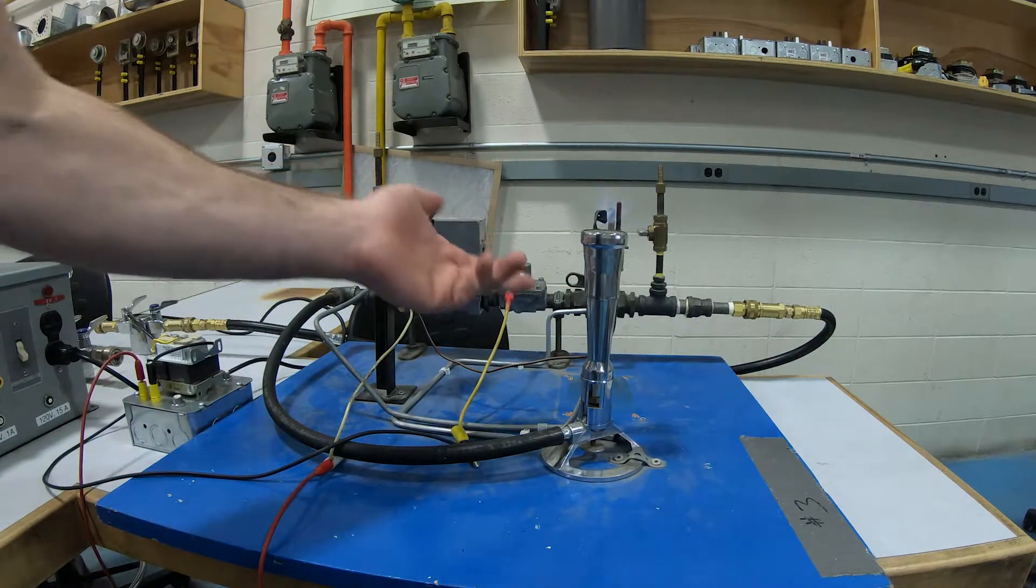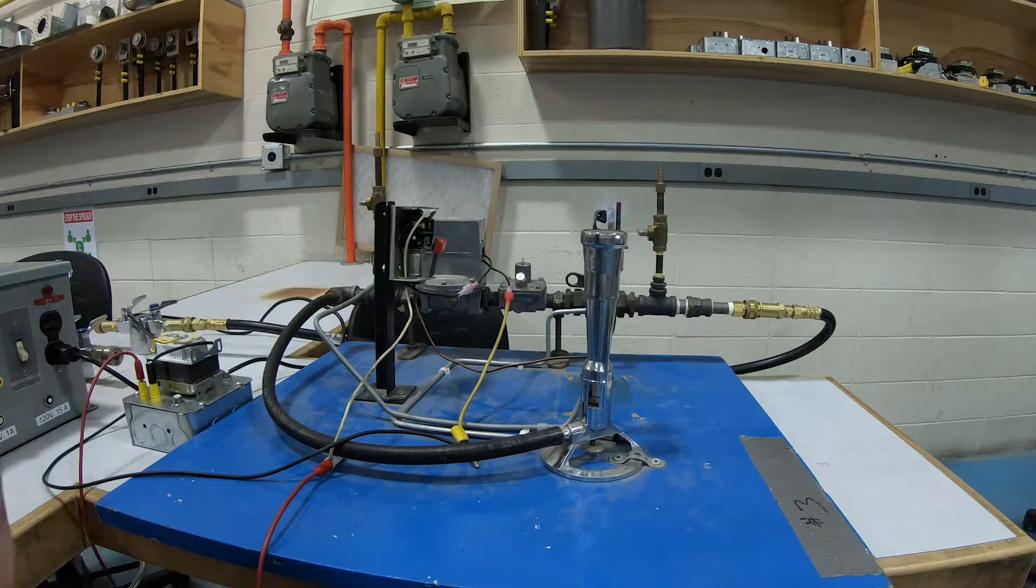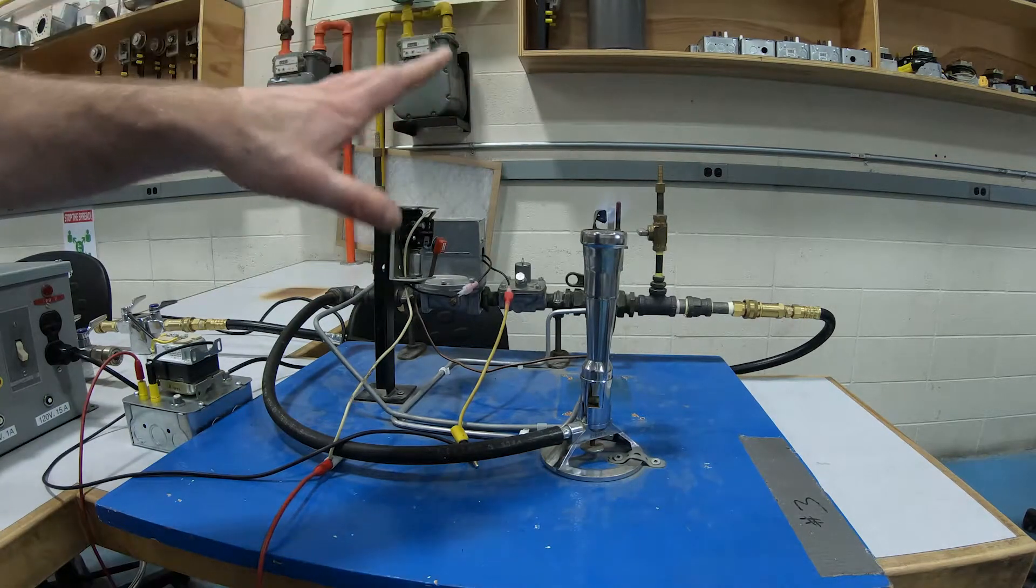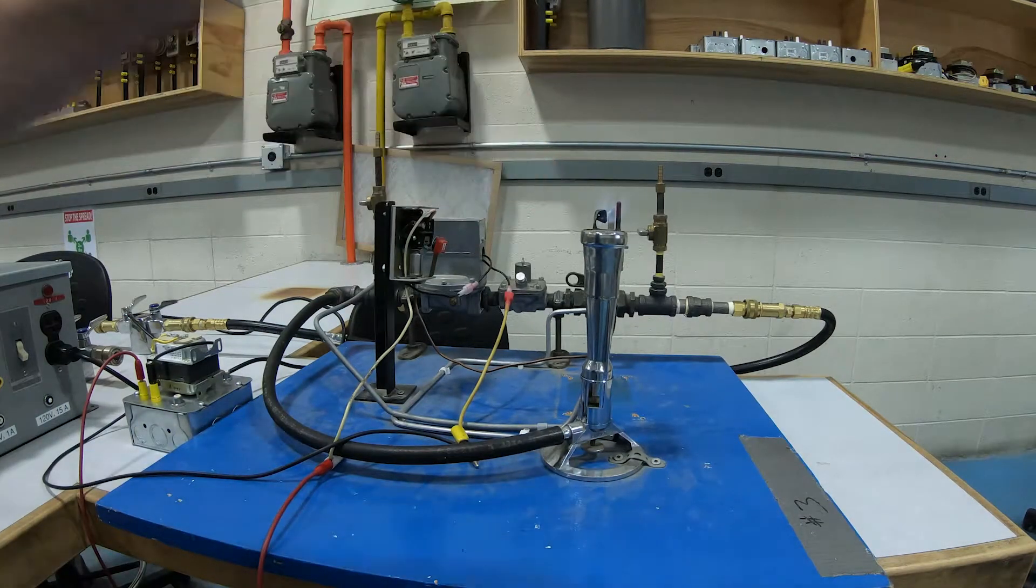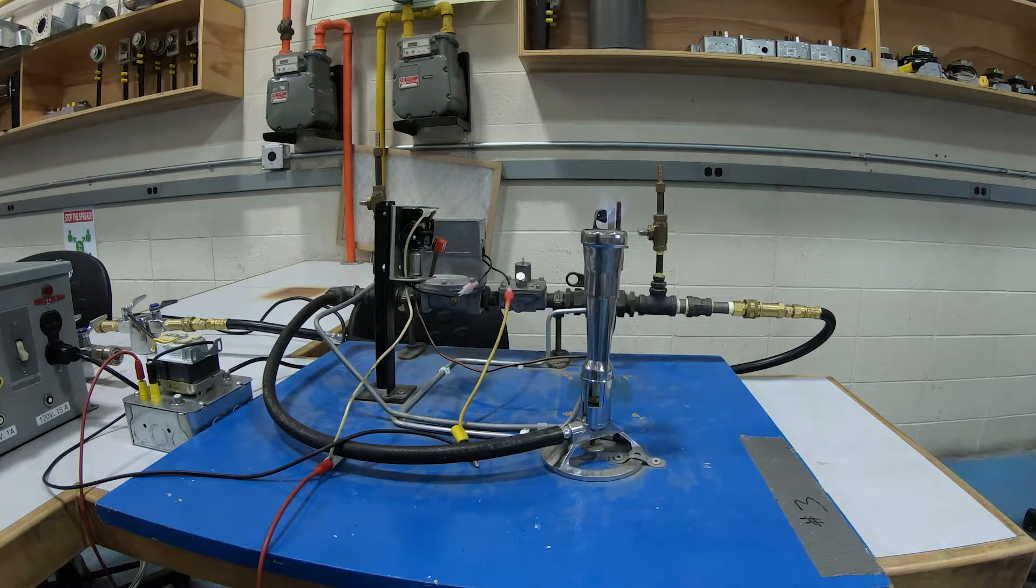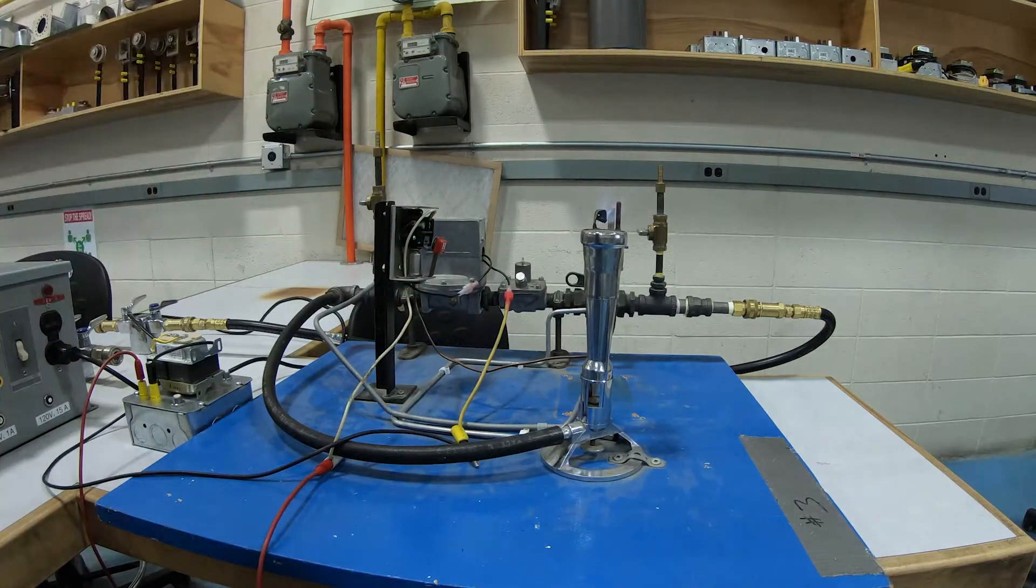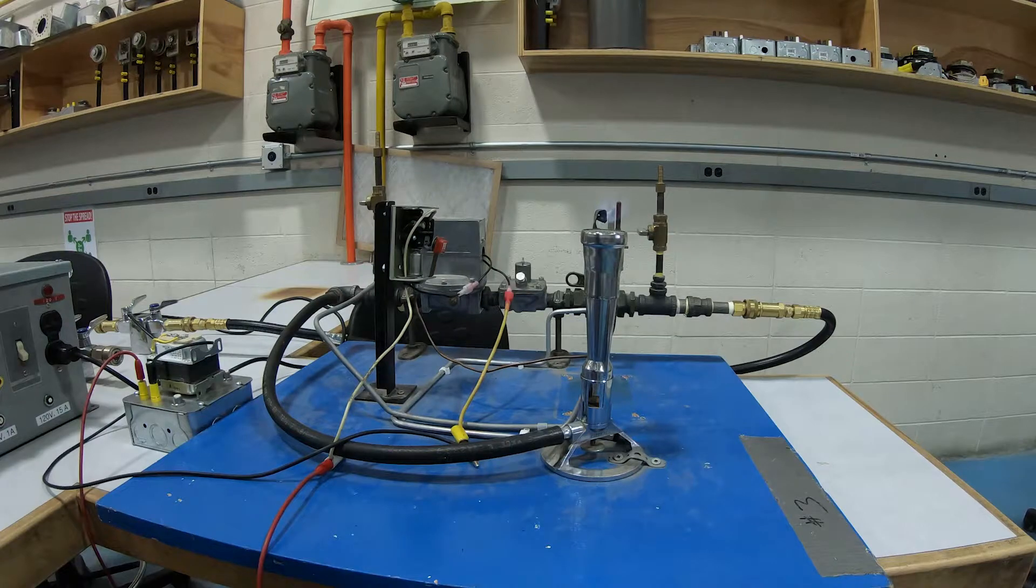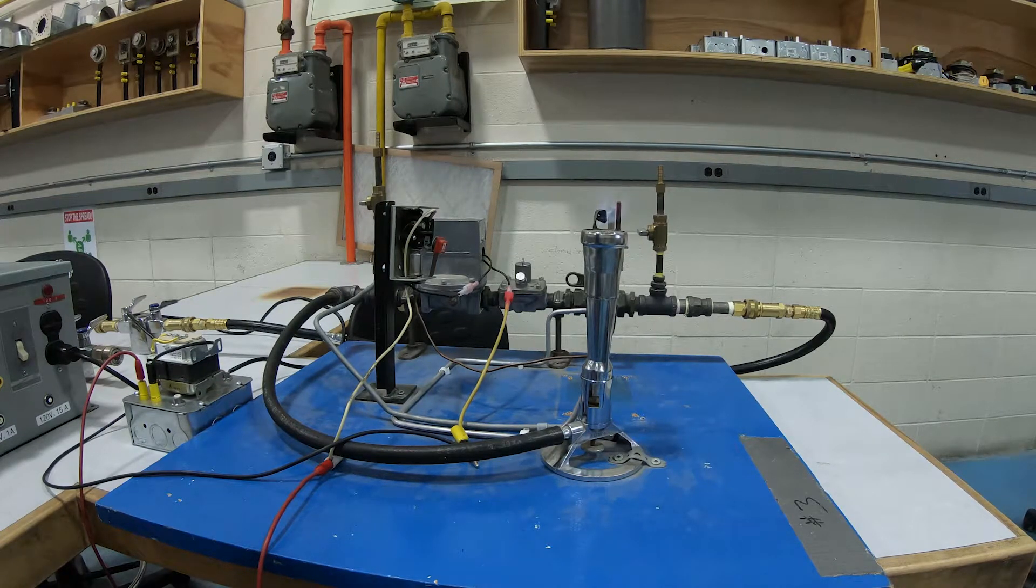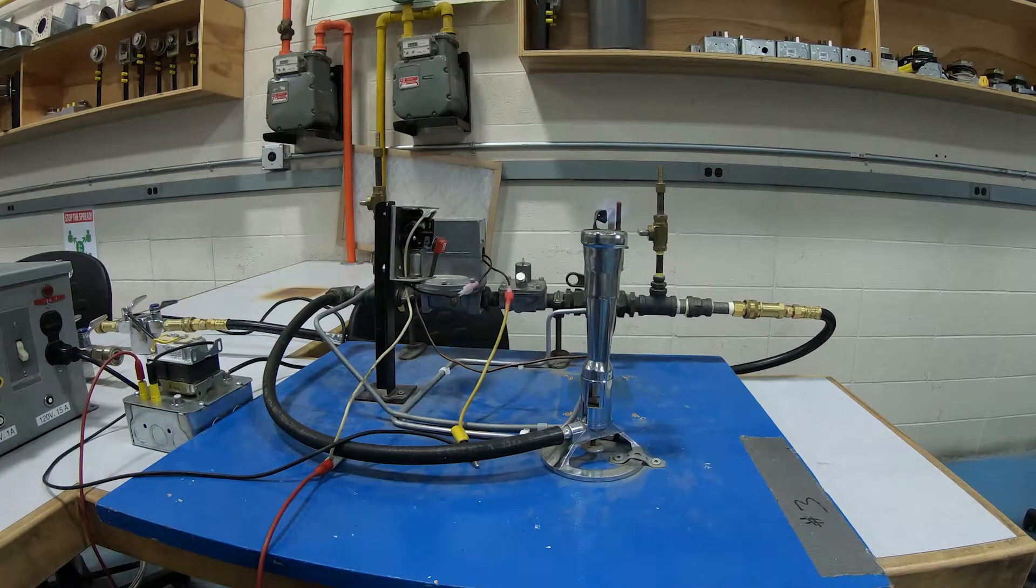There is still a thermocouple, but if that thermocouple is turned right off or if the thermocouple is not working or if that pilot assembly blows out, it will just continually flow gas through there. There's nothing stopping the flow of gas through this pilot tubing. Seems a little silly, yes. I know that's what you're thinking. And where we use it, God knows where, other than in really old stuff. But it's still legitimate and is still allowed by our gas code.